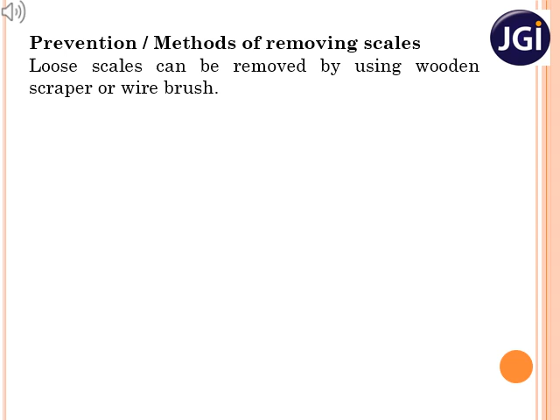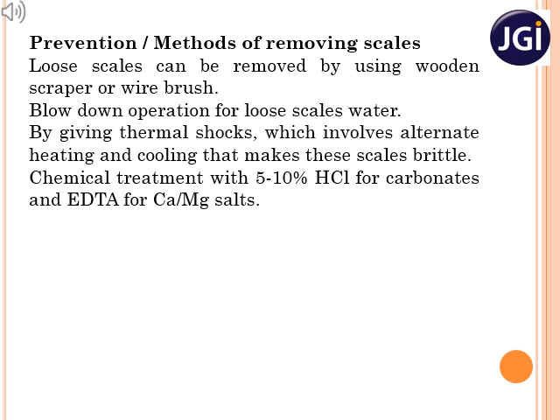Loosely held scales can be easily removed by using a scraper or brush. Alternate heating and cooling of boiler pipes makes the scale brittle and hence scales can be broken and removed. The carbonate scales are removed by treating with 5 to 10% hydrochloric acid, whereas calcium or magnesium ions or salts are removed by EDTA complexation methods.